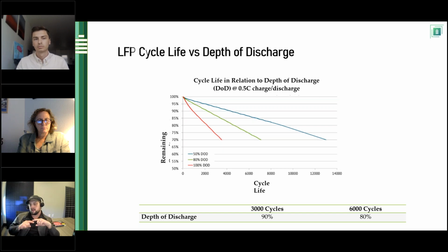And that's because the depth of discharge is a variable, it's never consistent. You can always expect more cycles. Well, you should, if designed correctly, expect more cycles from the battery than what the manufacturer says in a given situation, unless you're abusing the battery. In that case, where you're maybe at 90% or 100% discharge regularly, you certainly are not going to get the life off the battery, right?